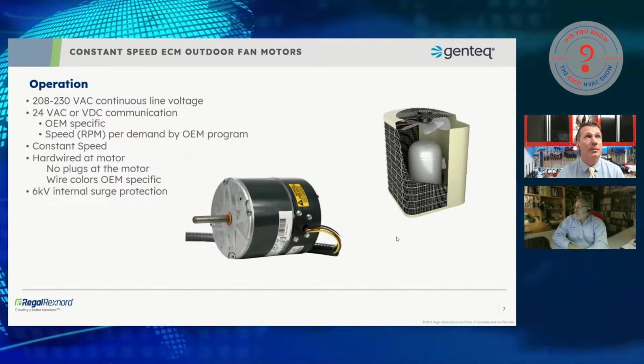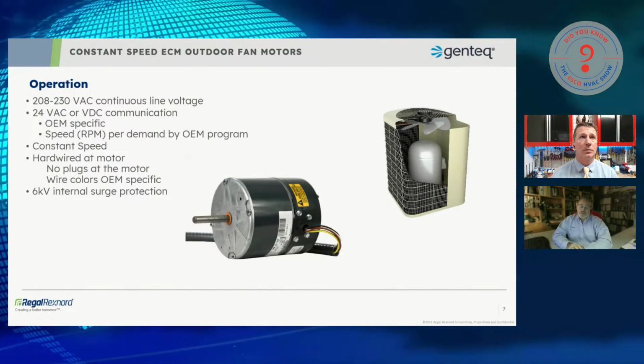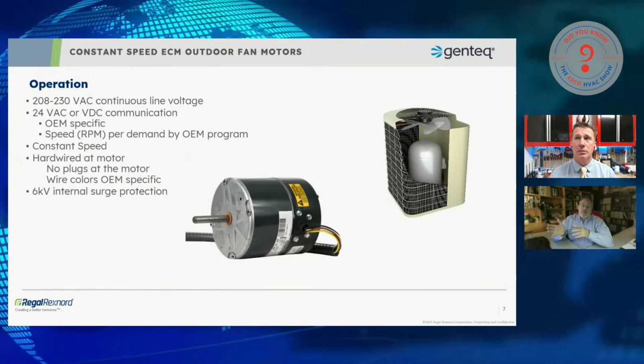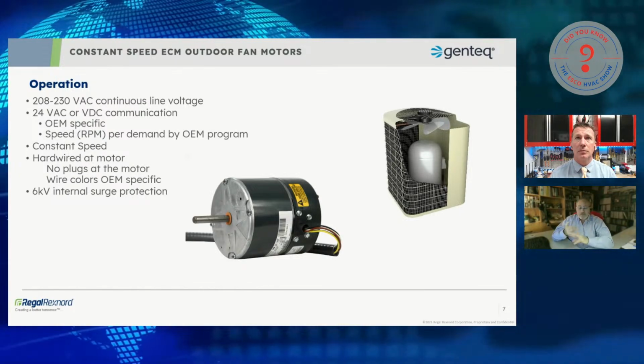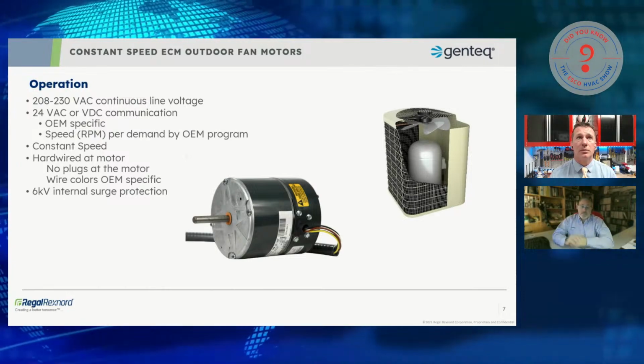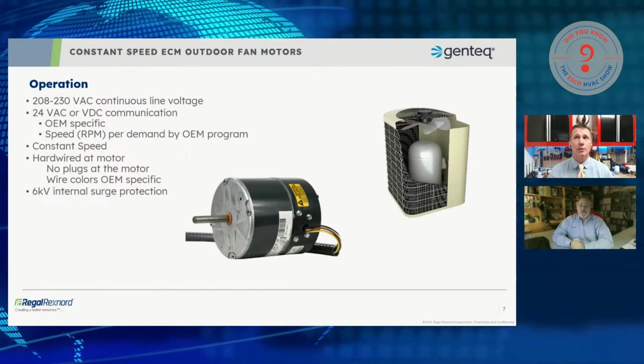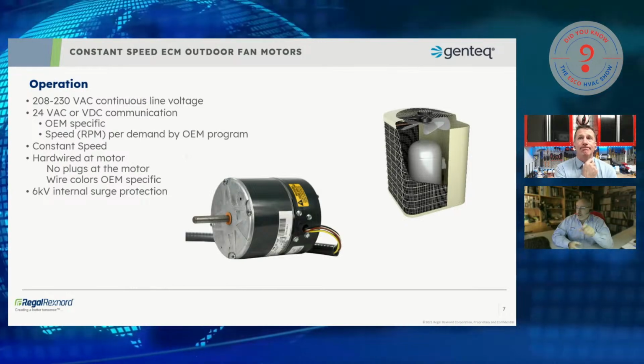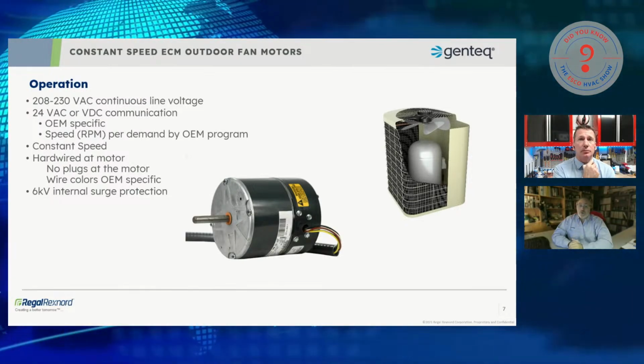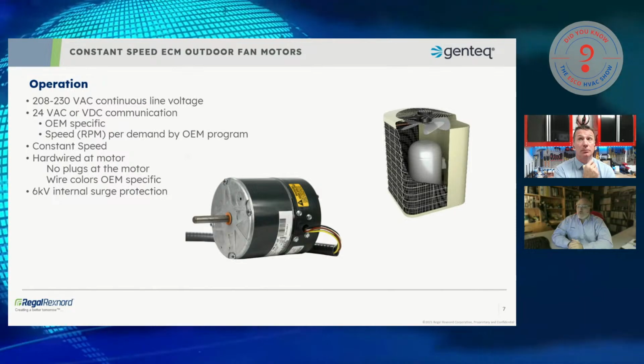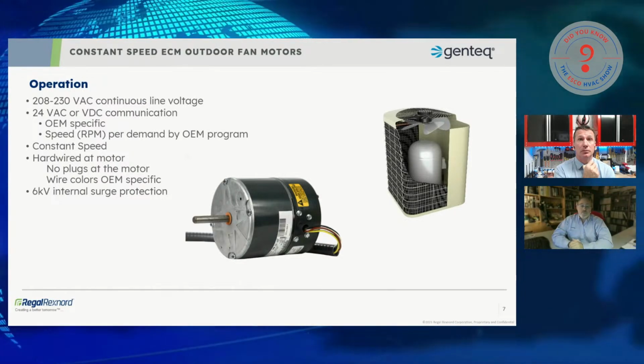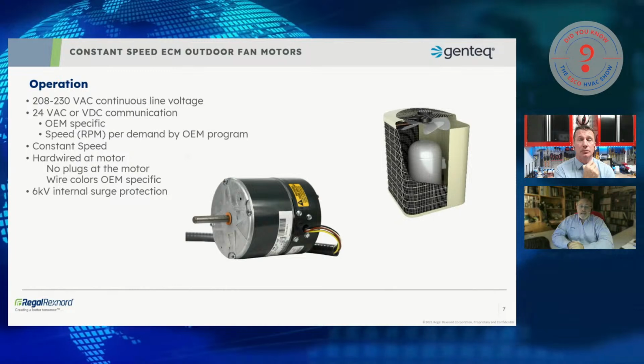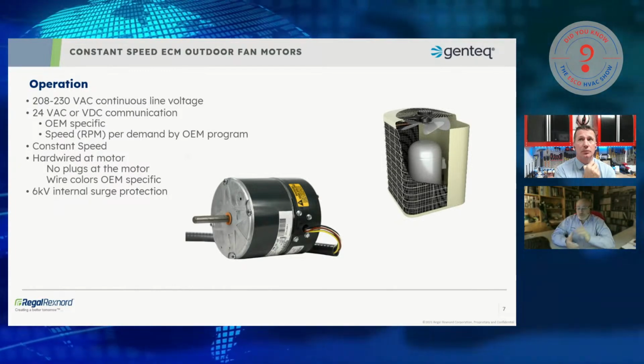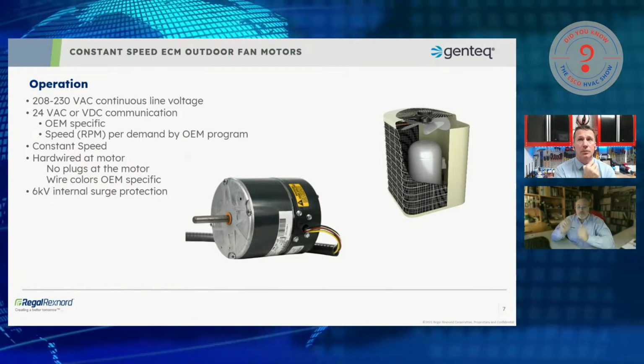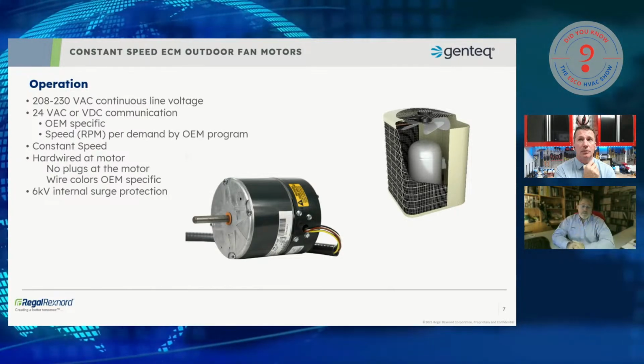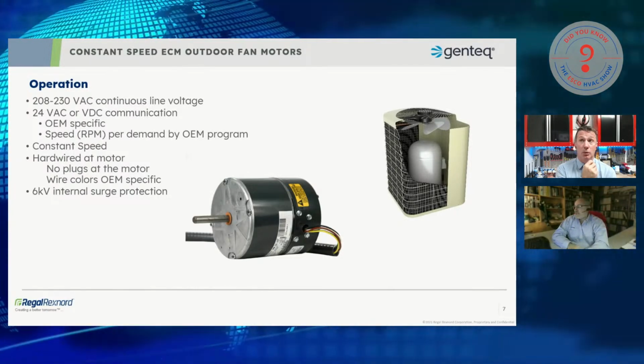Awesome. Fantastic. So again, hardwired at the motor. So unlike the indoor blower motors, no plugs. There's not going to be a 16-pin plug or a 9-pin plug or any external plugs, because that would be a source for water to intrude to the motor. Hardwired out. The wire colors, I should mention, are OEM specific. So I don't use any wire colors here, but if you learn on one particular brand of unit, don't assume the blue and the yellow, for example, are always speed and common. The wire colors could change from one manufacturer to another.